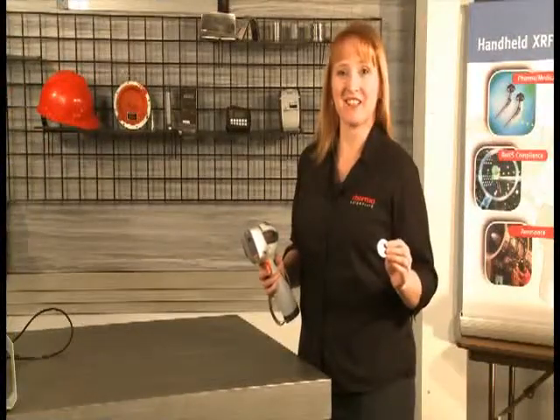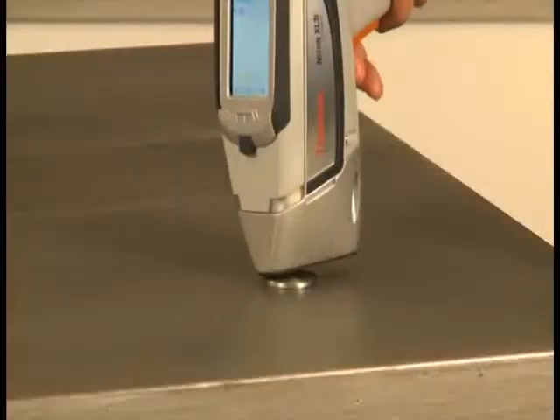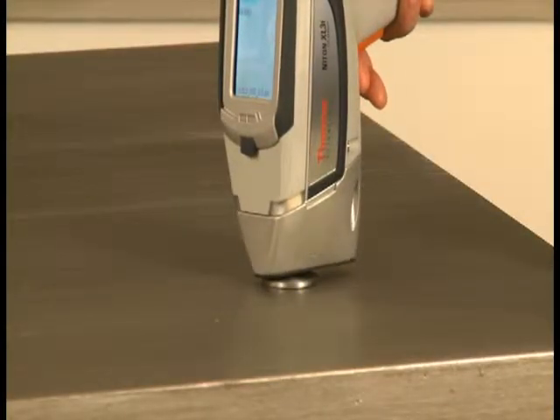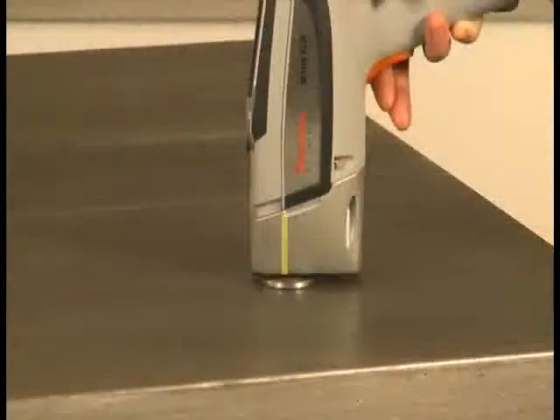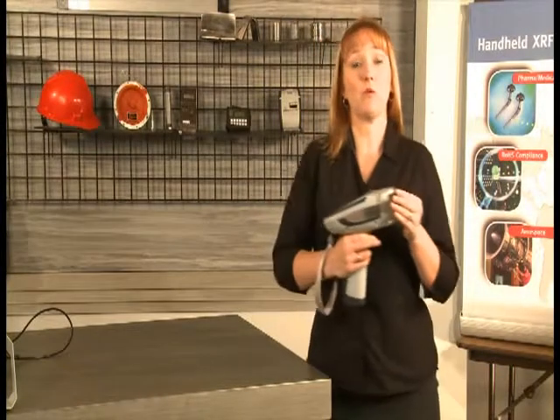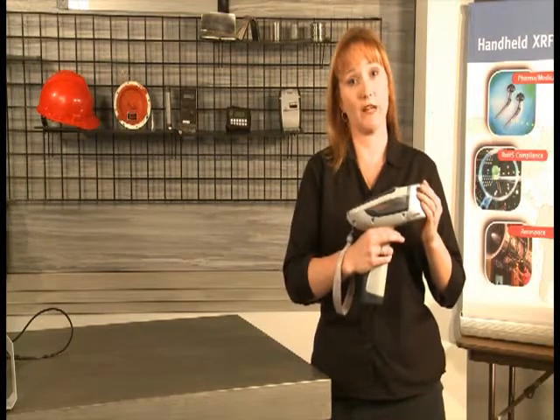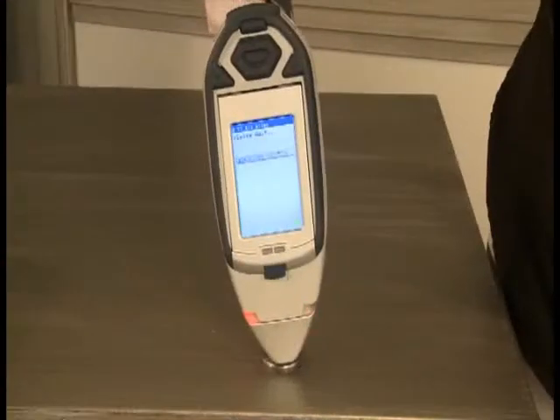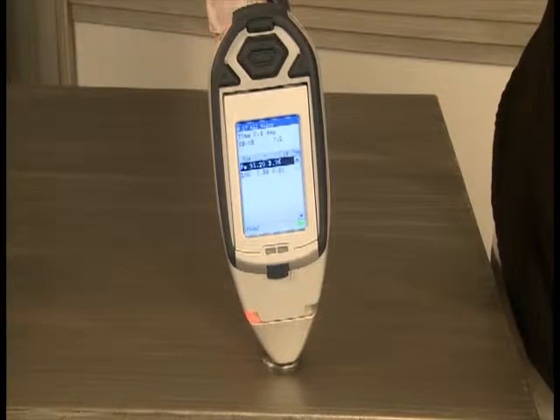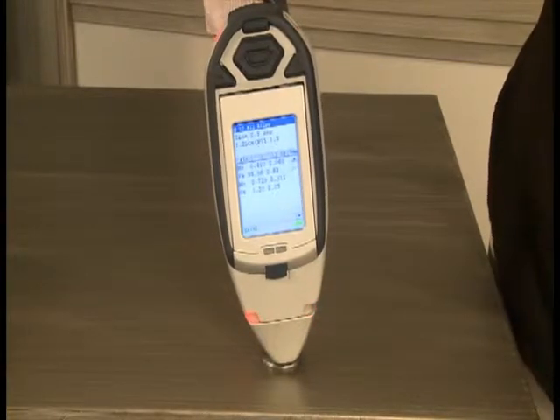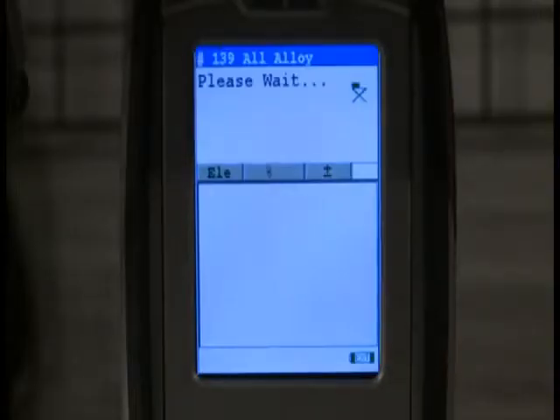We are now ready to test the check sample. To do this, you will place the front end of your instrument on your sample. Note the locator markings on either side of the analyzer front end that indicate the vertical location of the measurement window to aid you in positioning the analyzer on the sample. It is very important to note that for radiation safety purposes, you must never hold your hand over the sample. As we initiate the measurement, note the display, as shown here, indicates the elapsed time. You must keep the trigger pressed during the entire measurement.